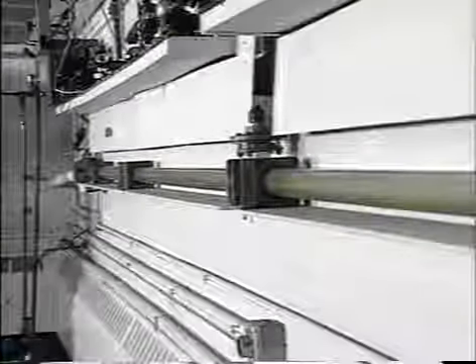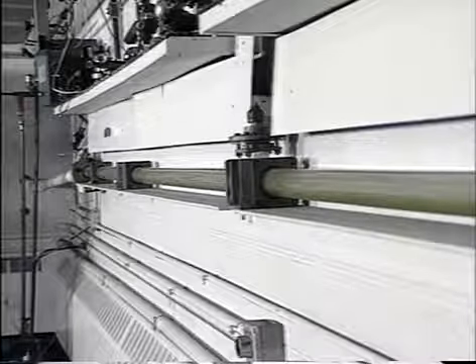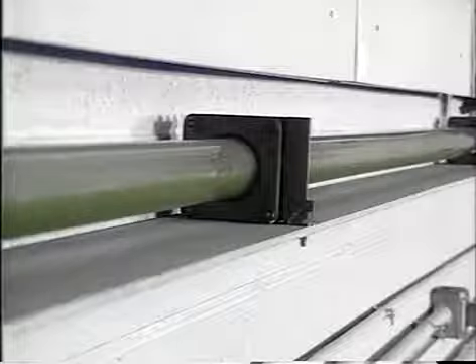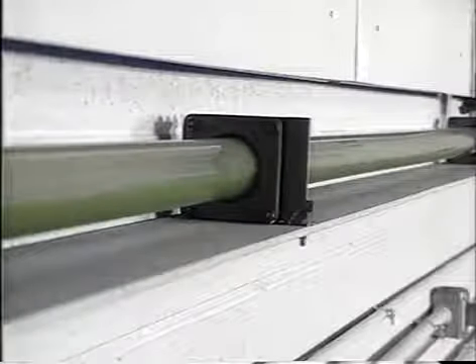We are increasing the speed of the water flowing through the pipe by virtue of the velocity of the gas flowing across its surface. Observe now as the compressed airflow increases. The waves formed on the surface of the condensate become higher. Further increasing the airflow causes the waves to block off more of the cross-section of the piping until a seal is formed, completely closing off the pipe.